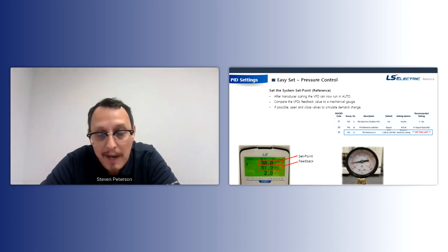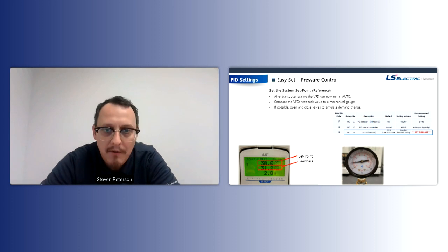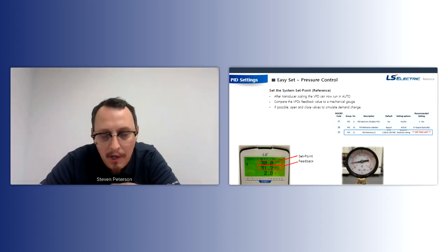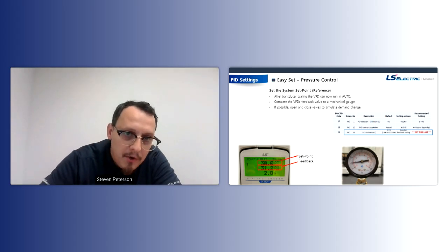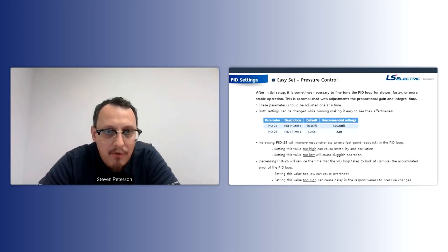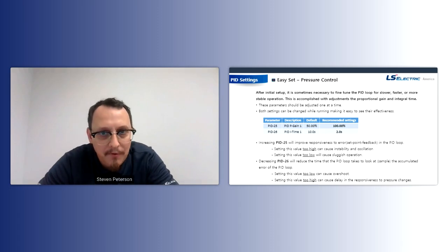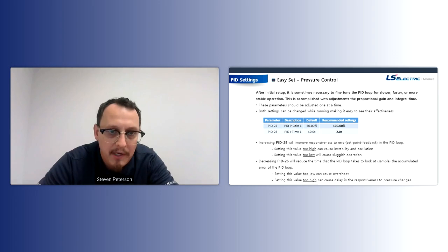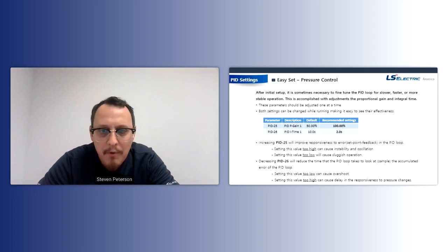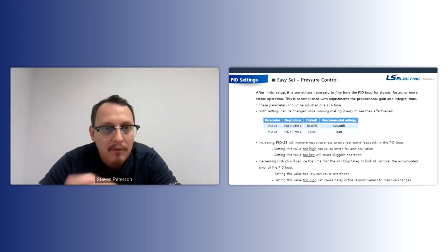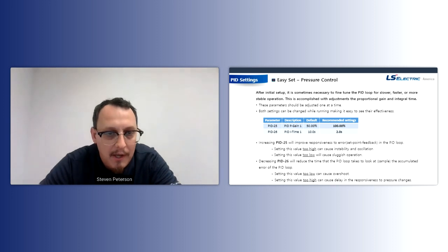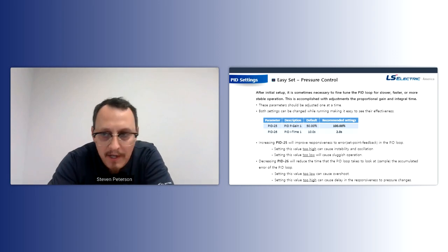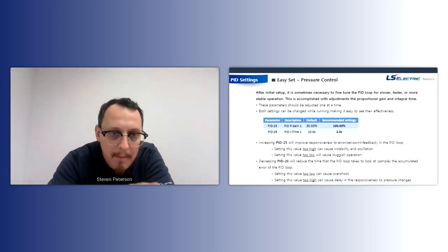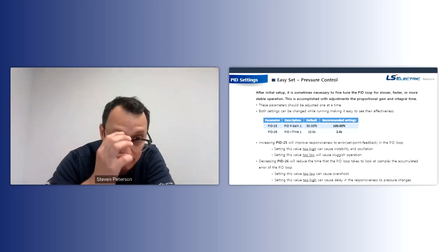While you're running this, it's also a good time to open and close valves and simulate demand change. Then you'll see the drive running up and down to maintain that pressure. While you're doing that, it's good to note that we could change our P gain and our I time. As I mentioned, people call it a PID loop, but a lot of times you're only talking P and I, proportional and integral time. Those are the two parameters you'd most likely adjust if you need to fine tune the PID loop, to make it slower or faster, or just make operation stable in general. These aren't hidden anywhere in the drive's parameters. They're listed right in that macro group, so you just go down the list and program whatever you need.